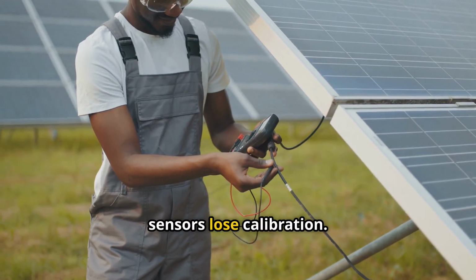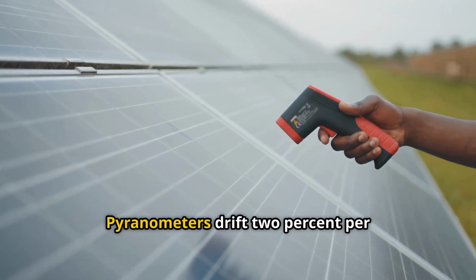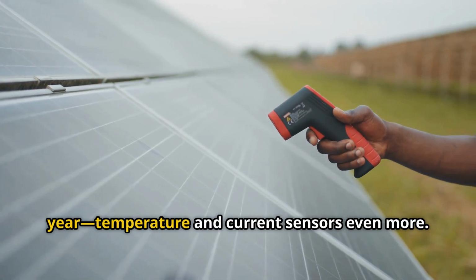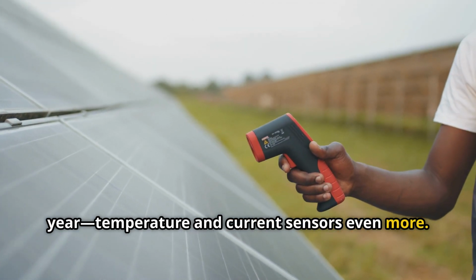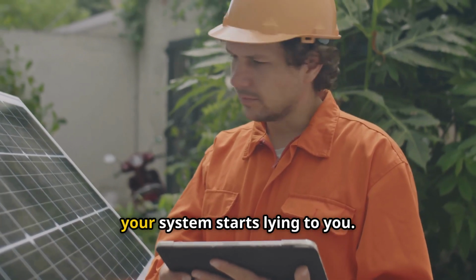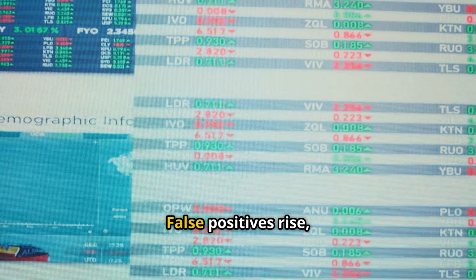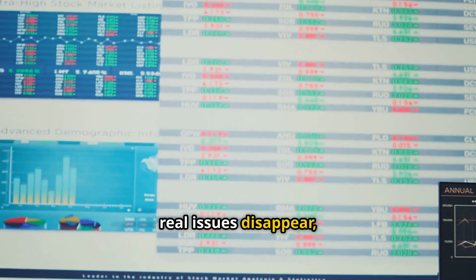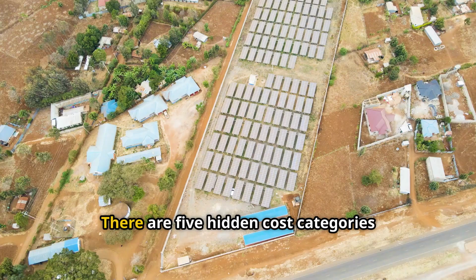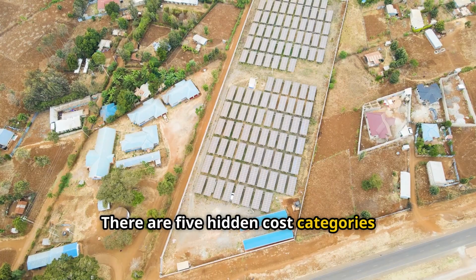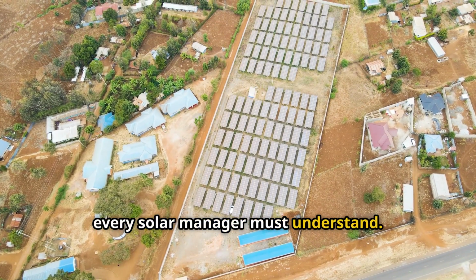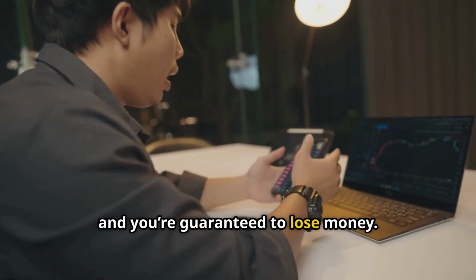Over time, sensors lose calibration. Pyranometers drift 2% per year. Temperature and current sensors even more. Without recalibration tracking, your system starts lying to you. False positives rise, real issues disappear, and your maintenance plan collapses. There are 5 hidden cost categories every solar manager must understand. Ignore these and you're guaranteed to lose money.